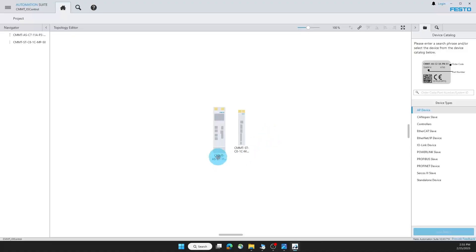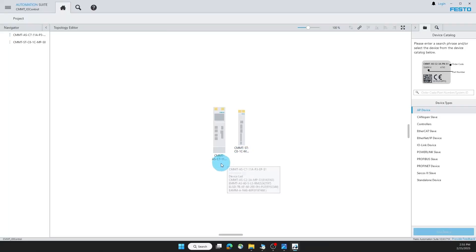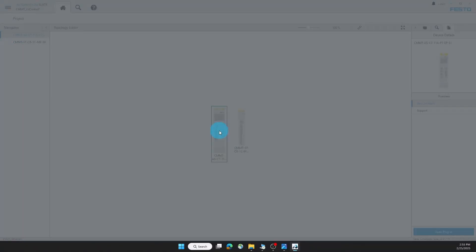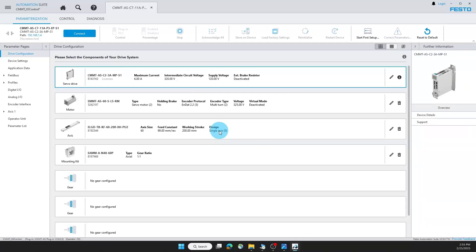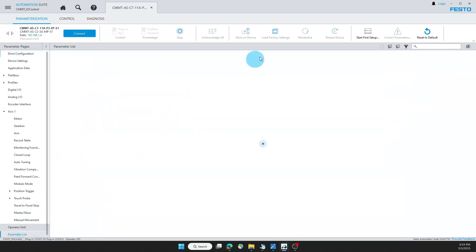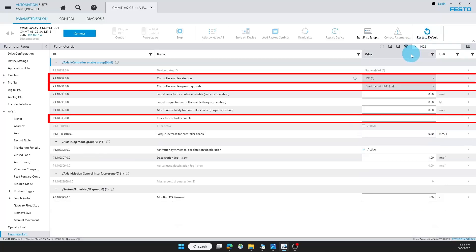Now notice here that there's two different drives set up and this is very important for whichever drive type you're using. For this project, I'm going to use a CMMT-AS servo so I'm going to double-click on this one. Before connecting to your drive, you want to make sure that you change all these settings as well as anything else that applies to your application. Although some parameters are set in the archive, we'll want to make sure under parameter list, if you search 1023, there's three different parameters that we want to make sure we have set.